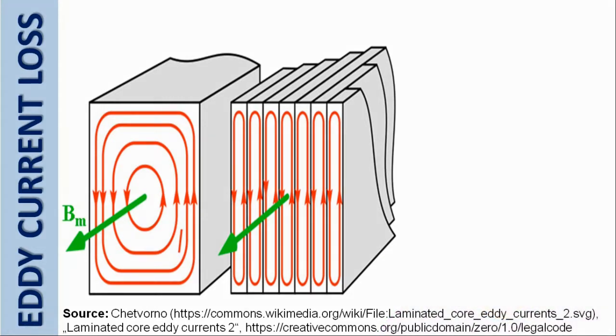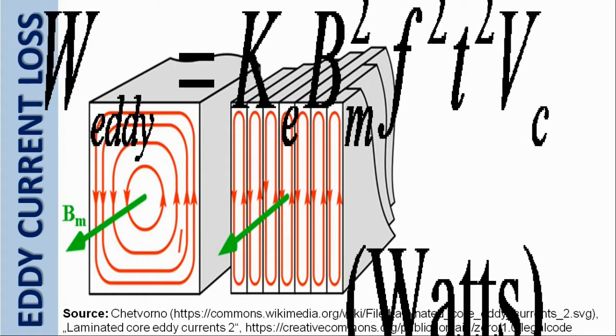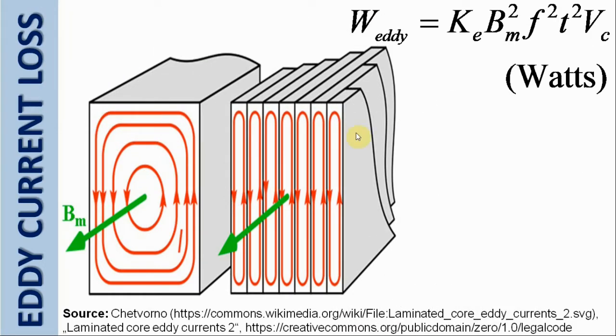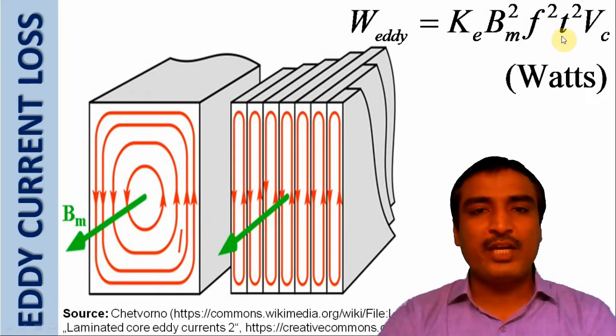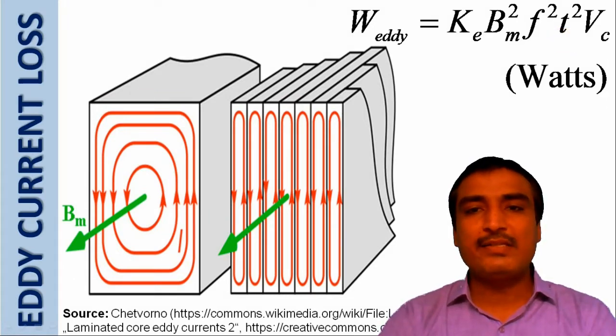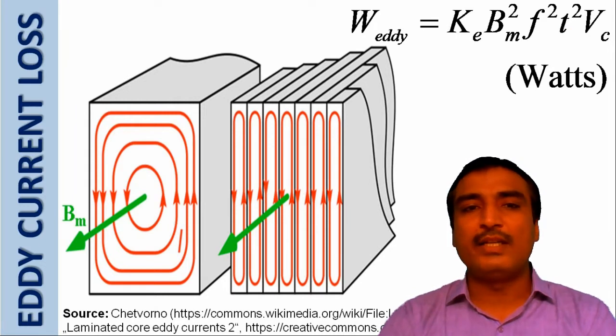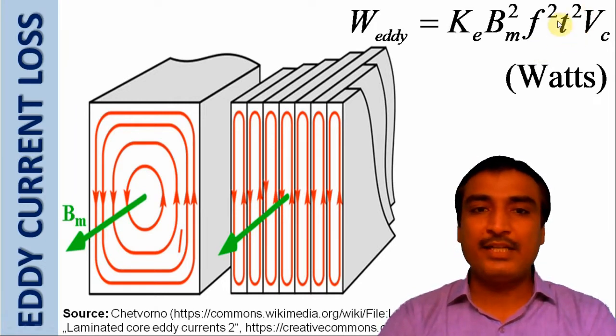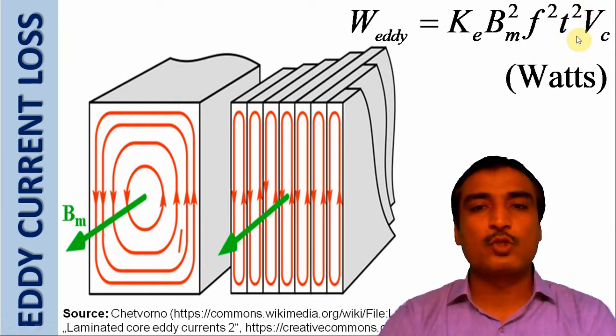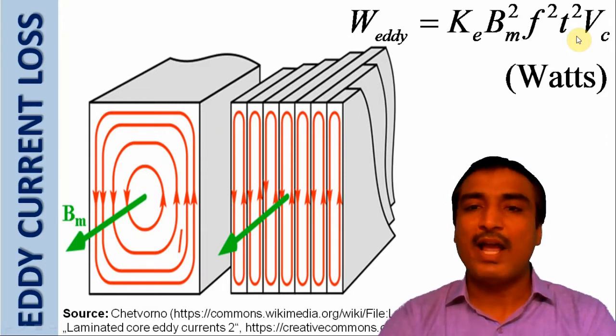This is the expression to calculate the eddy current loss. In this expression, Ke is a constant called the coefficient of eddy current, and its value depends upon the nature of the armature core material. Moreover, T represents the thickness of the core laminations. It is also worth noting that the eddy current loss depends upon the square of the lamination thickness. For this reason, the lamination thickness should be kept as small as possible.